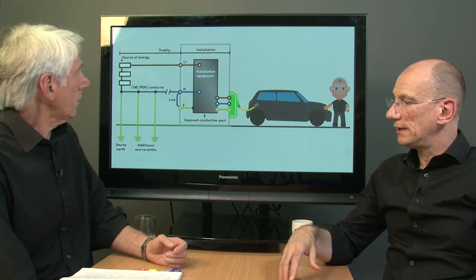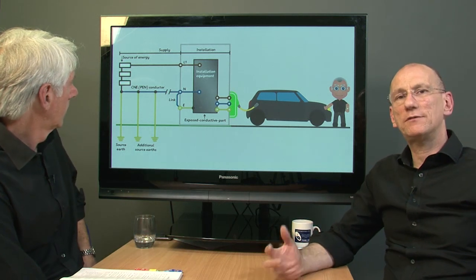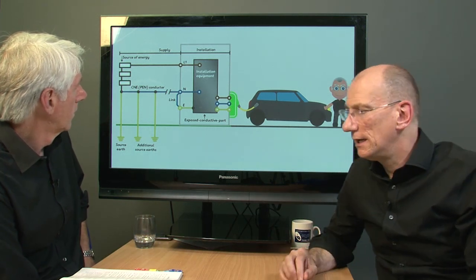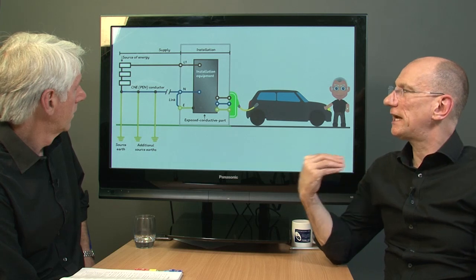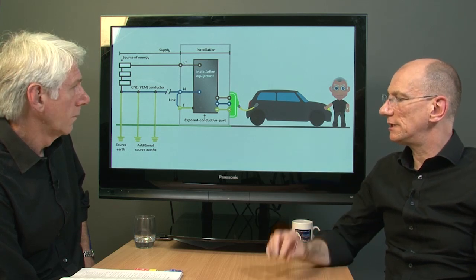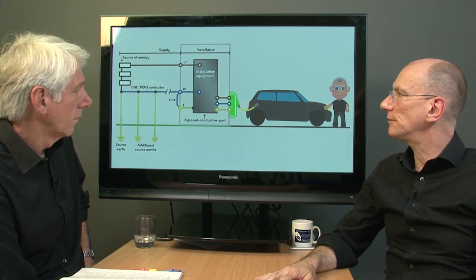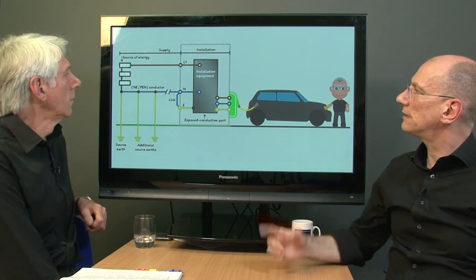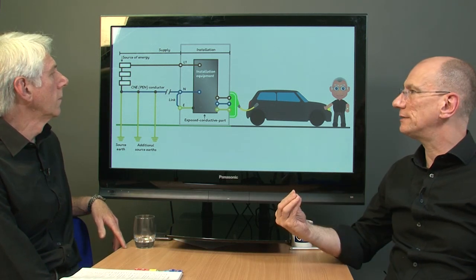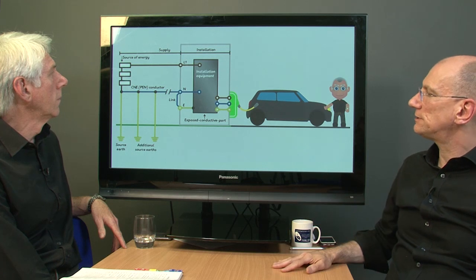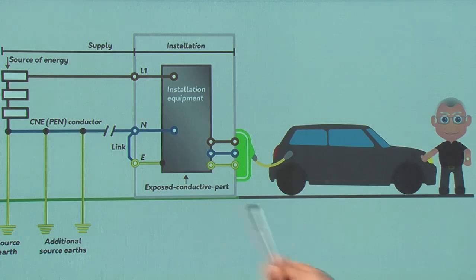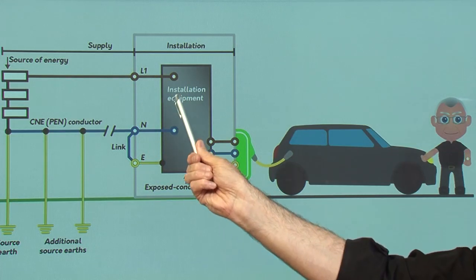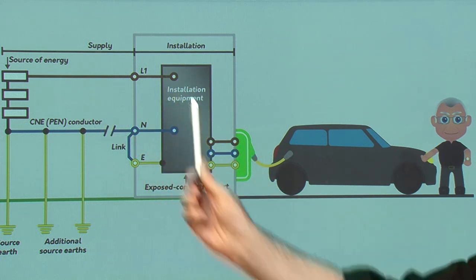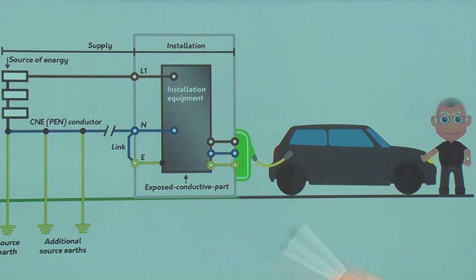In section 722, which covers electric vehicle charging points, there's a particular point made about TN systems, and in particular a PME scenario, and why there is a risk. This isn't spelt out in the requirements, but here's a nice picture to explain it. We have our supply coming into the installation, with a return path via the neutral, via the PEN conductor. That PEN conductor is an earth and a neutral combined.